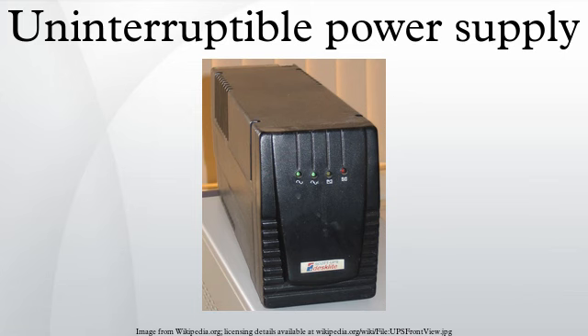Line interactive. The line interactive UPS is similar in operation to a standby UPS, but with the addition of a multi-tap variable voltage auto-transformer. This is a special type of transformer that can add or subtract powered coils of wire, thereby increasing or decreasing the magnetic field and the output voltage of the transformer. This is also known as a buck-boost transformer. This type of UPS is able to tolerate continuous undervoltage brownouts and overvoltage surges without consuming the limited reserve battery power. It instead compensates by automatically selecting different power taps on the auto-transformer. Depending on the design, changing the auto-transformer tap can cause a very brief output power disruption, which may cause UPSs equipped with a power loss alarm to chirp for a moment.